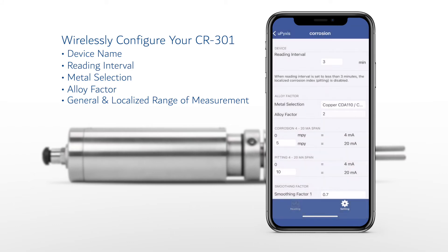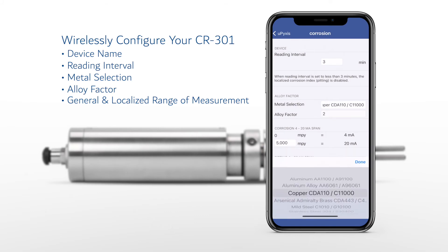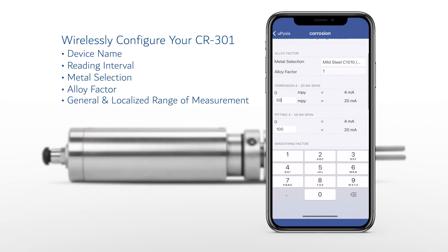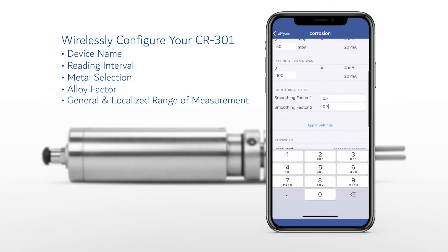Simply select the metallurgy of choice from the uPyxis drop-down list and the app will automatically assign ranges of measurement for general and localized corrosion, as well as alloy factors based on the metallurgy UNS code and common industry practices. Users may also customize the range of measurement to as high as 995 mils per year for general corrosion and 100 index for localized corrosion, assign a sensor name, program a customized metallurgy, and assign a unique alloy factor if desired.